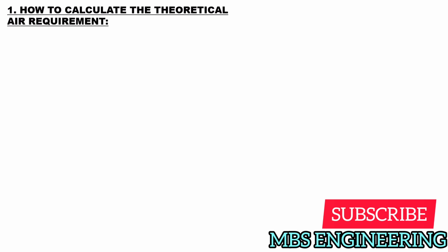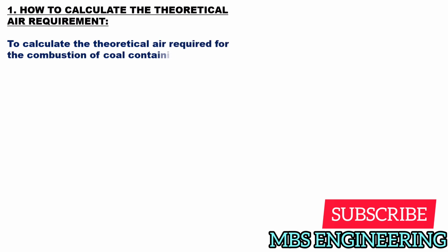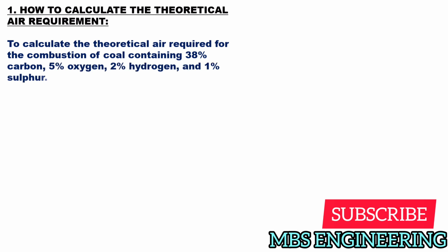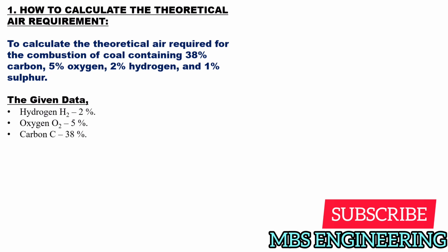Next, we will learn and understand how to calculate the theoretical air requirement. Next, let's learn the sample example in calculations. To calculate the theoretical air required for the combustion of coal containing 38% carbon, 5% oxygen, 2% hydrogen, and 1% sulfur. The given data: hydrogen, H2 is 2%. Oxygen, O2 is 5%. Carbon, C is 38%. Sulfur, S is 1%. The following formula is used to calculate the theoretical air requirement.